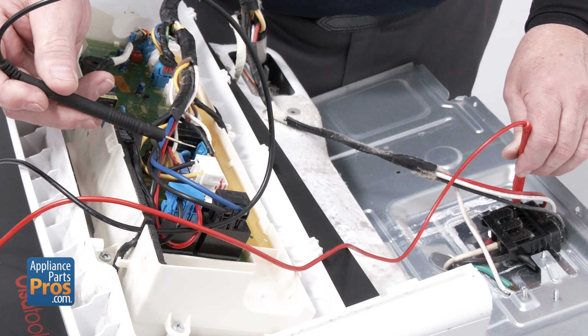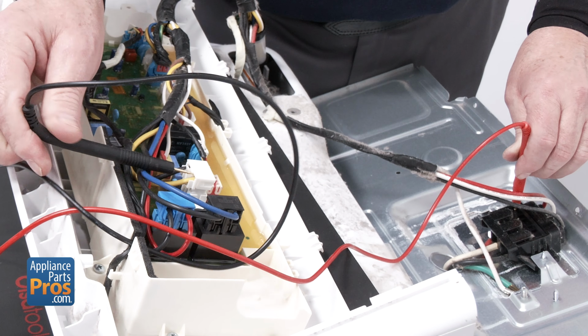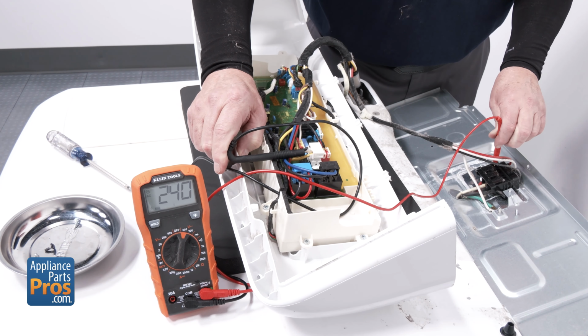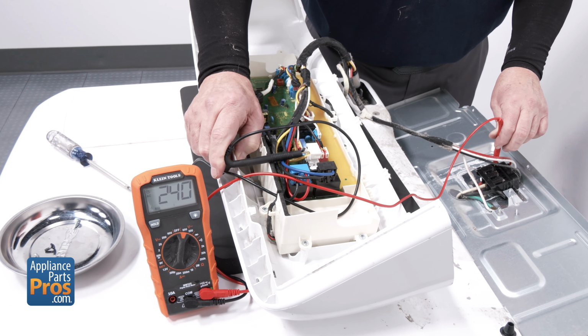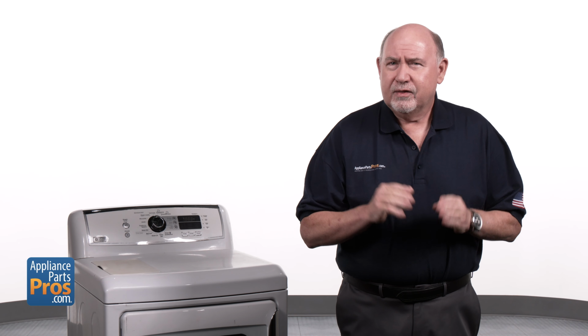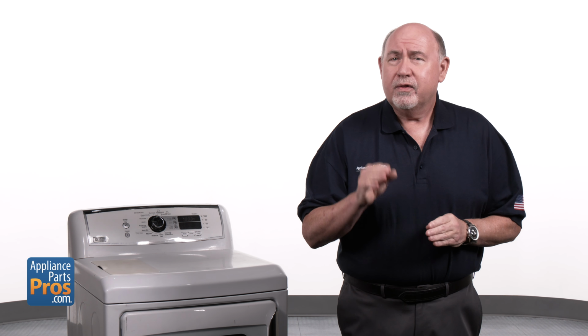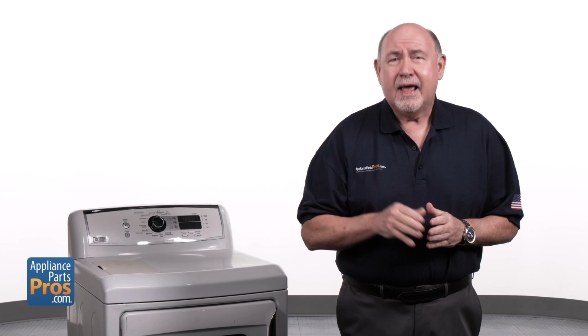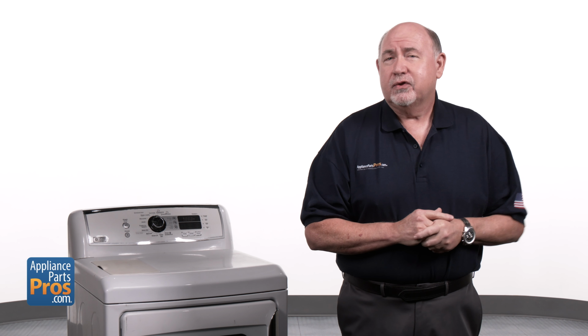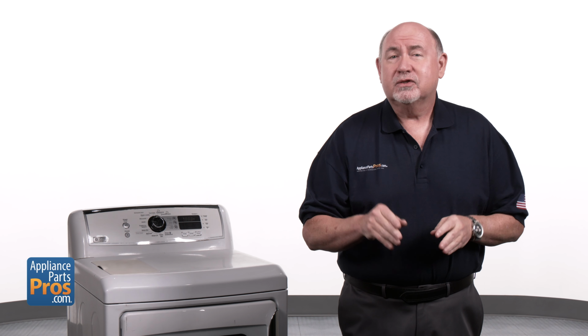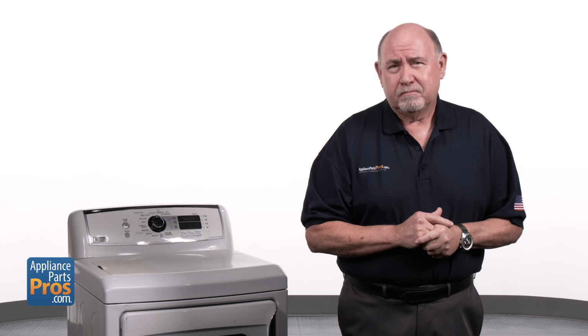Next, move to the yellow wire at the white relay. Again, check to L2—you should also see 240 volts there. If you're not getting those readings, that tells you one of the relays isn't closing. It's not sending voltage to the heating element, and that means the control board's failed.